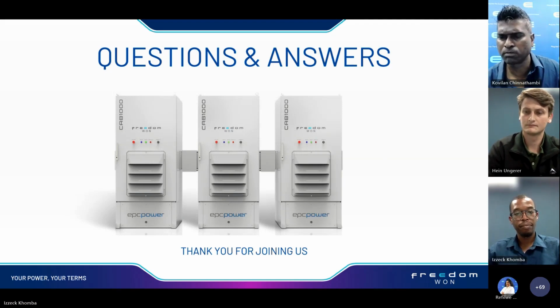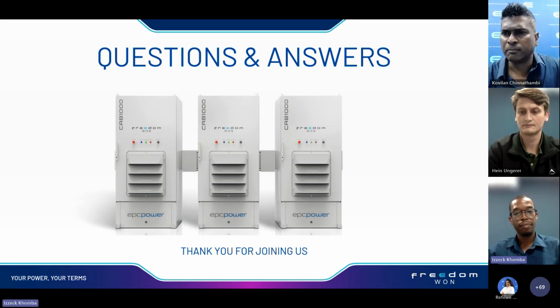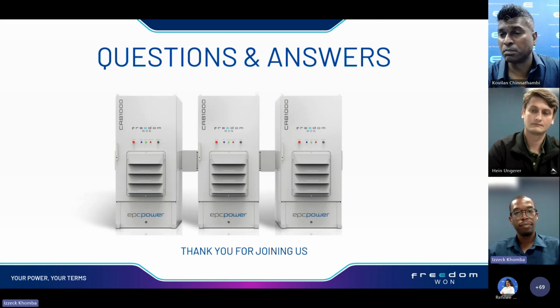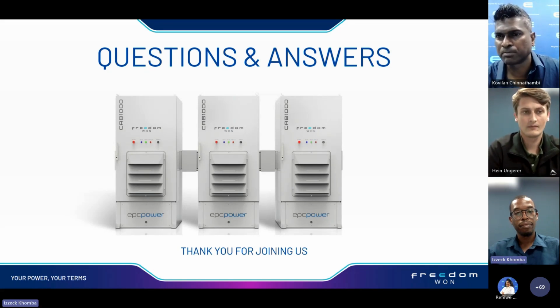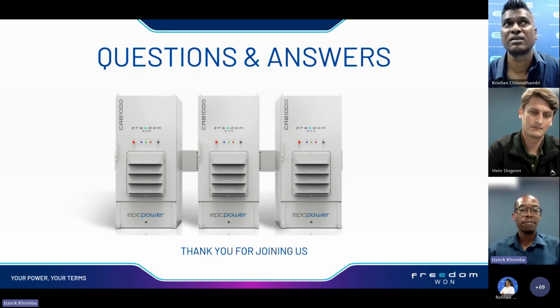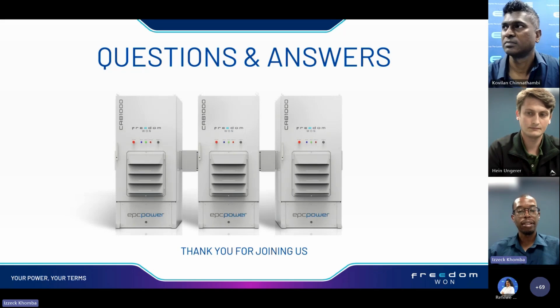So we've got another question on the sizing of the inverter and motor rating. Ben asks, should the inverter be 6 times the motor rating? I think Hein covered this in his previous response. If you look at the motor, the amount of reactive power it requires during startup and the transient should be such that it does not exceed the rated power of the inverter.